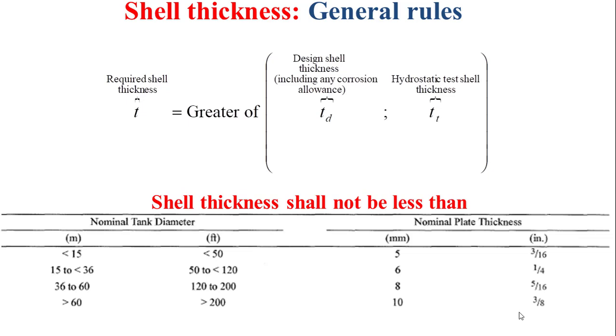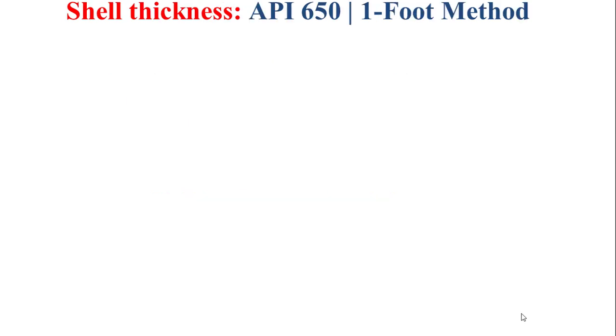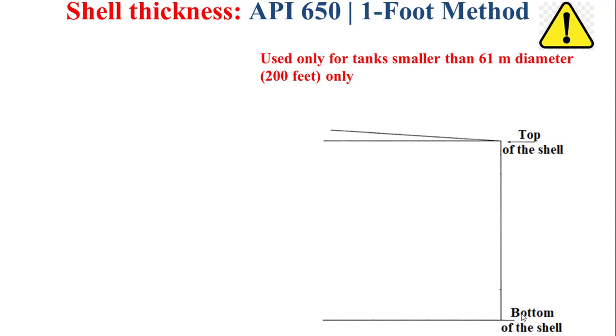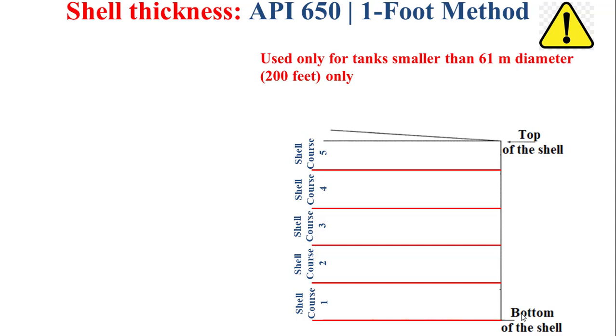Even if the calculated shell thickness is lower than these minimum values, we have to take those values as the minimum shell thickness. The one-foot method is used only for tanks smaller than 61 meters in diameter. Also, the shell thickness is not constant from bottom to top since the pressure is not constant, so we have to subdivide the shell into several shell courses and calculate the appropriate thickness for each.